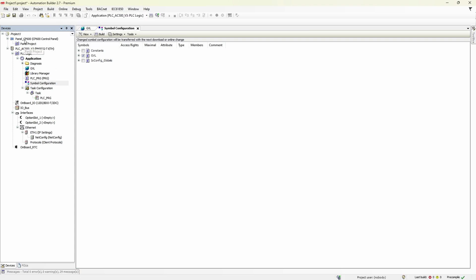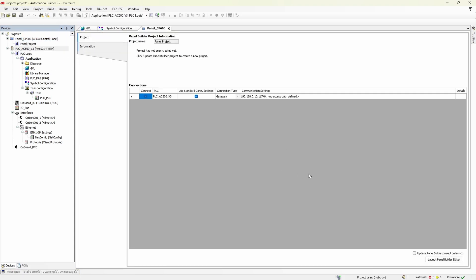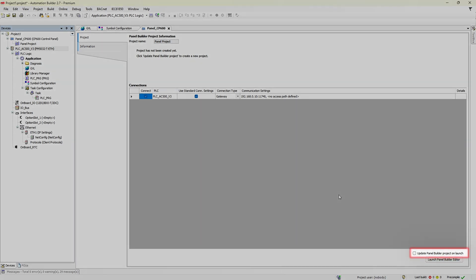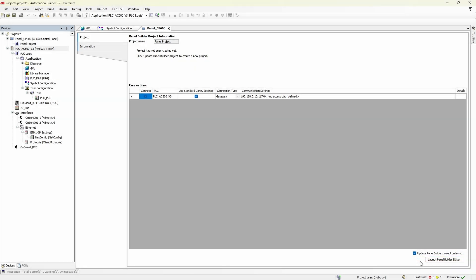Next step we go to CP600 panel item. Tick the checkbox update panel builder project on launch. By doing that we'll create tags in HMI project automatically. This checkbox is not available in basic version of Automation Builder, so you would need to do tag import in panel builder manually. But other than that, the approach is the same.